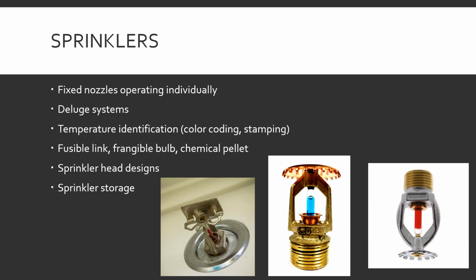Sprinkler head designs. Now, there's a whole lot of designs. And the easy way to tell is looking at the little reflector here for the water. And the orientation of these pictures actually helps. So we're going to start over here on the left. This is a wall mounted. This is one that's not mounted on the ceiling. It's up towards the top of the wall where the wall meets the ceiling. And obviously, it really doesn't do any good for water to be coming out the top, hitting the wall, and not doing anything. So they got this little deflecting shield, so water comes down and it goes out to the sides, but it's not spraying the ceiling, not really accomplishing anything.